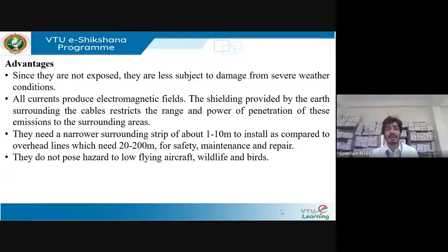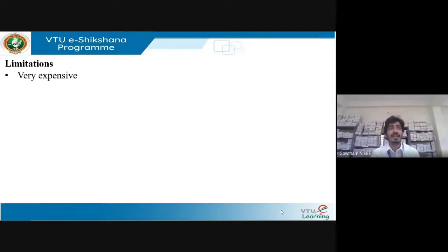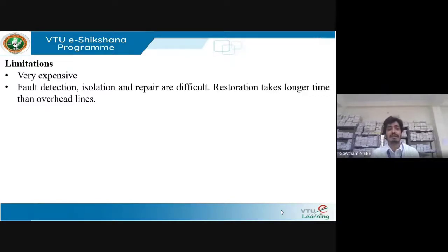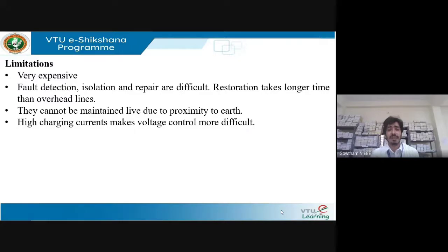UG cables do not pose a hazard to low-flying aircraft, wildlife, and birds. They are not easily prone to theft, illegal connections, or sabotage. Very few faults can occur. Limitations: they are very expensive, fault detection is difficult since they are underground, and restoration takes longer than for overhead lines. They cannot be maintained live due to the proximity effect, and high charging current makes voltage control more difficult.